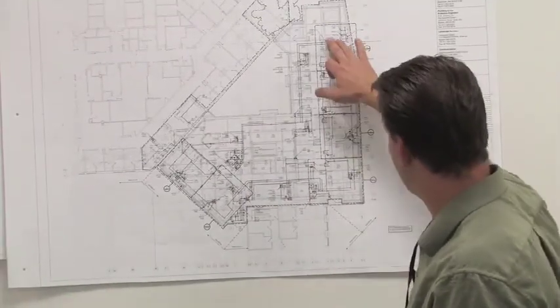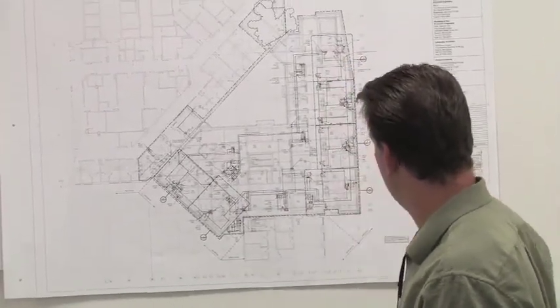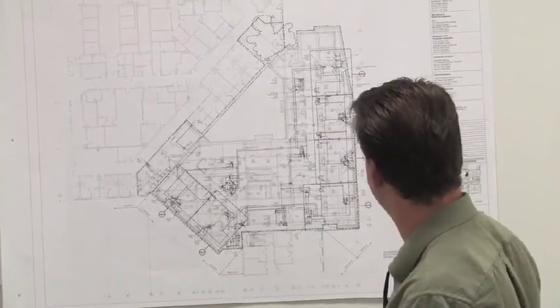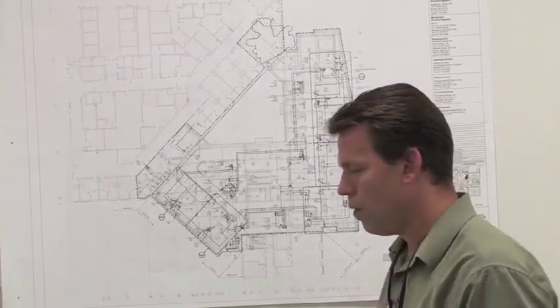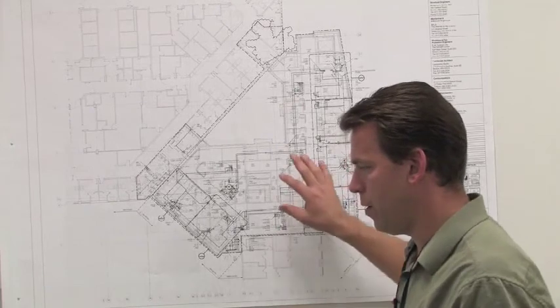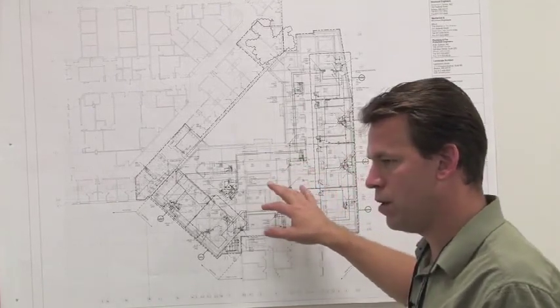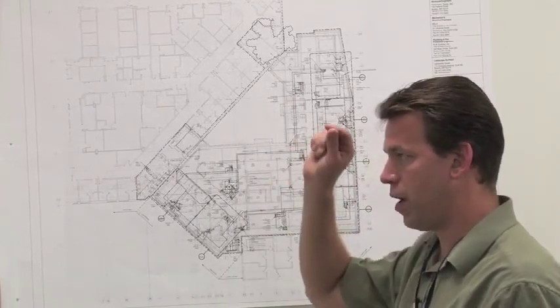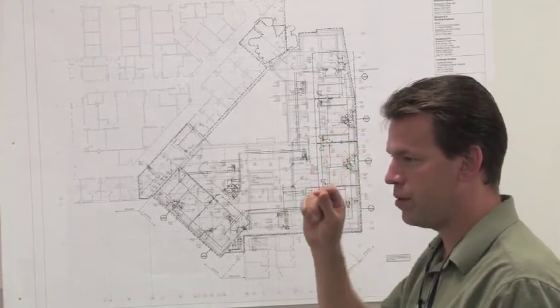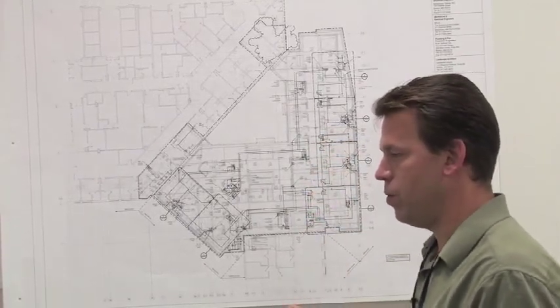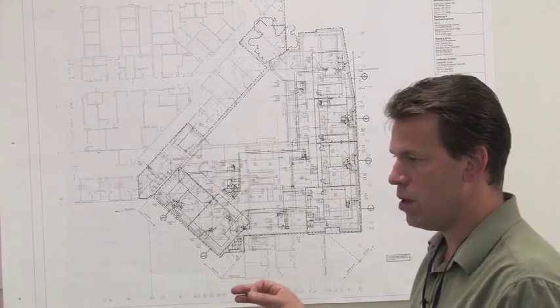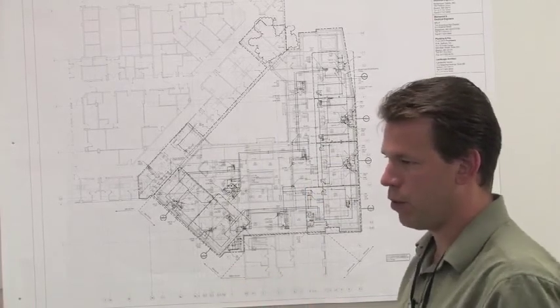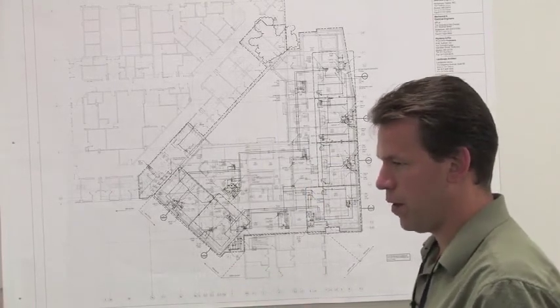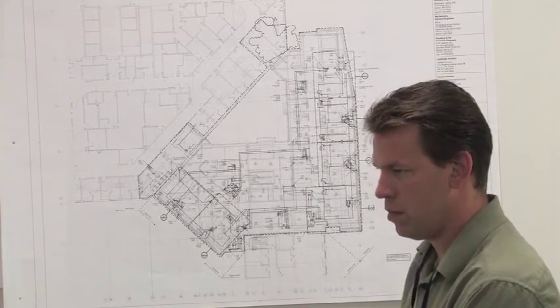So all med gas and everything comes out of that closet, right? That gas is coming out of here as well, yes. For the med gases, all of your zone control valve boxes will have shutoffs in the ceiling prior to the box, so that if you have a renovation, you can take that box out without shutting your floor down. You just shut it off with those valves. Do they have tampers on them? They will have locks on them, locked in place.